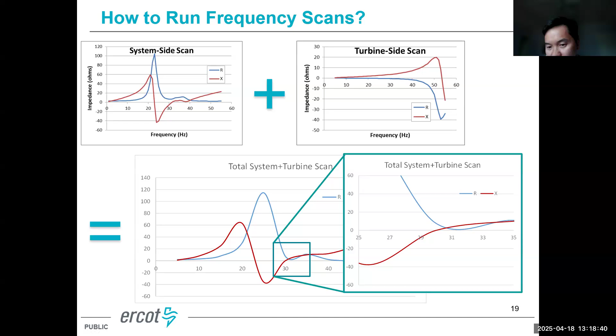How to run the frequency scan? For the grid side, since it's RBR, we have to use a perturbation analysis to do the frequency scan. The idea is to inject a wide-band noise signal voltage and current at the sub-synchronous frequency spectrum, then run FFT analysis to calculate the impedance at the sub-synchronous spectrum.